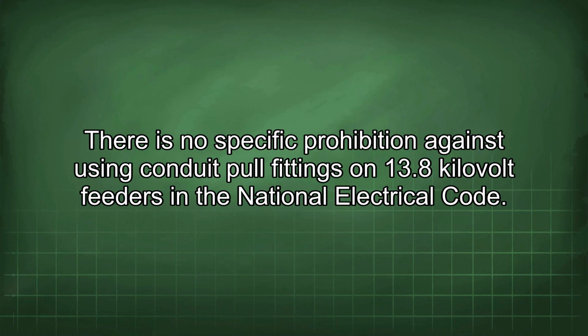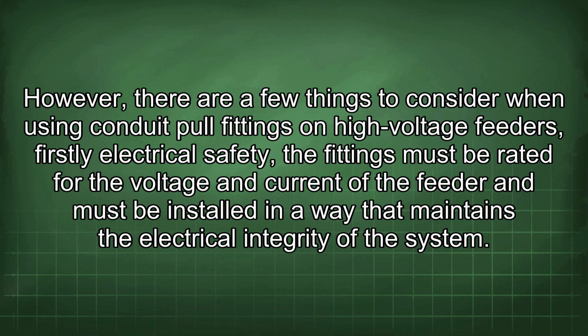There is no specific prohibition against using conduit pull fittings on 13.8 kilovolt feeders in the National Electrical Code. However, there are a few things to consider when using conduit pull fittings on high voltage feeders. Firstly, electrical safety. The fittings must be rated for the voltage and current of the feeder and must be installed in a way that maintains the electrical integrity of the system.